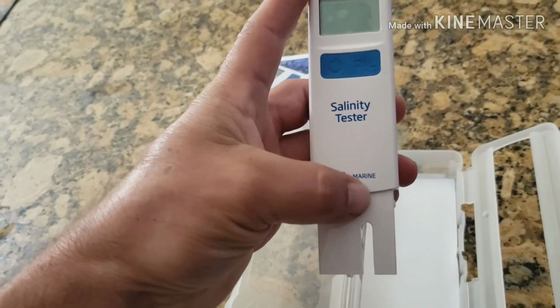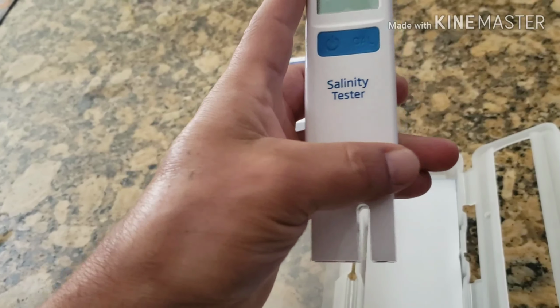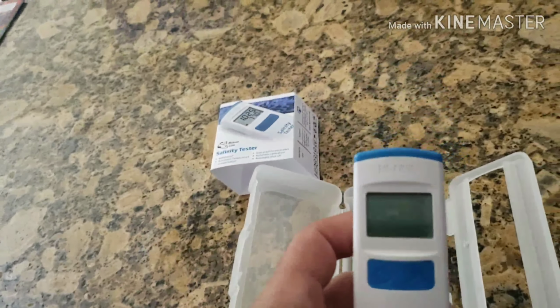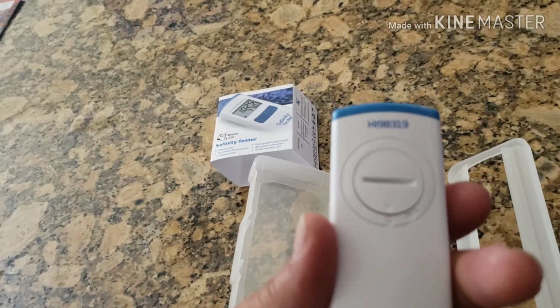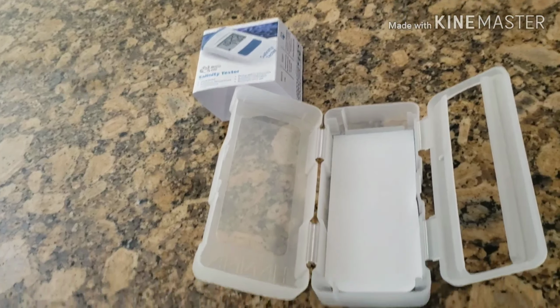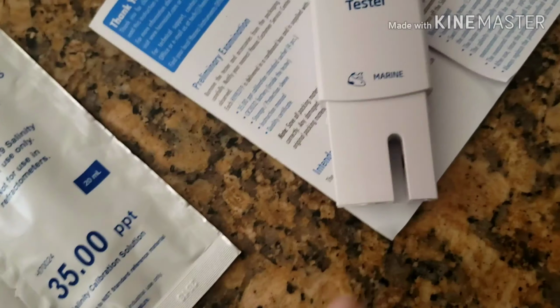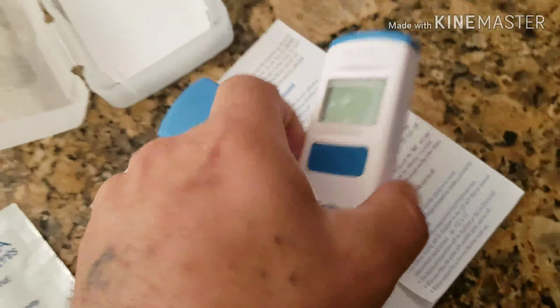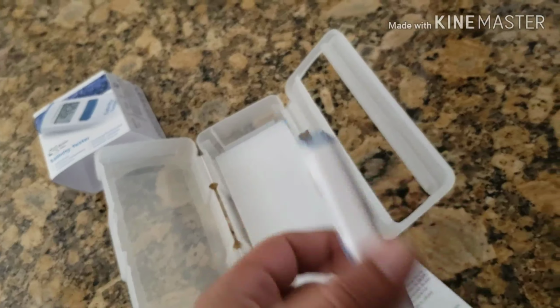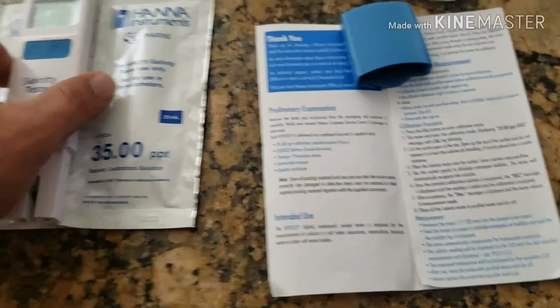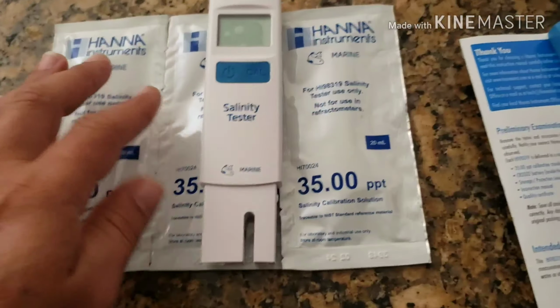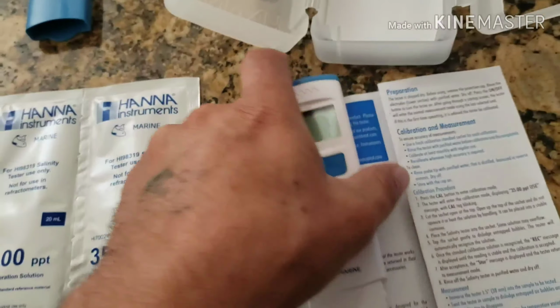Now when you dip this in the water, you do not want to dip further than this cap line, although the whole unit is waterproof if you accidentally drop the unit in the sump or the tank. So first thing you want to do is rinse the probes off, dry it completely, maybe give it a couple little shakes to get the water out of there. But make sure you rinse it off using RO or distilled water, and before you calibrate or use. And you need to do it after every use as well.